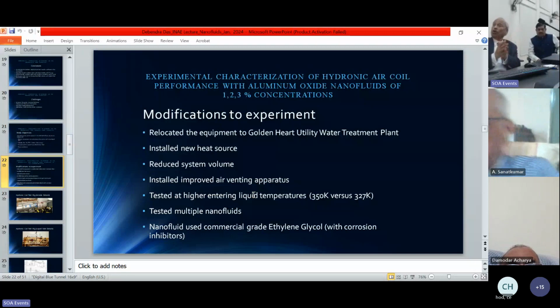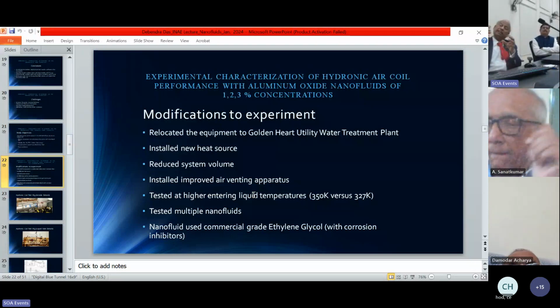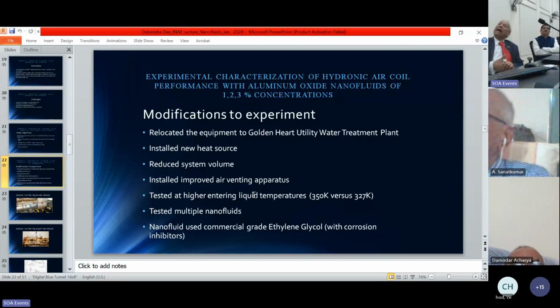We reduced the liquid volume so that we have less entrapment and less collection at corners, bends, and valves. We installed an improved air venting apparatus, putting an air vent on the top so that we can remove the air bubbles, and tested at a higher entering liquid temperature. Initially, we used to test at 327 K. We increased to 350 K because the manufacturer said that would cover a broader range and a broader number of clients. And we tested multiple concentration nanofluids, 1 to 3%.